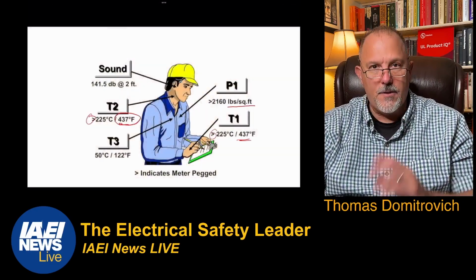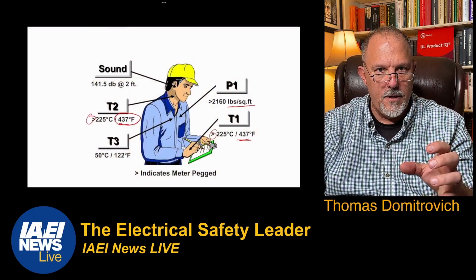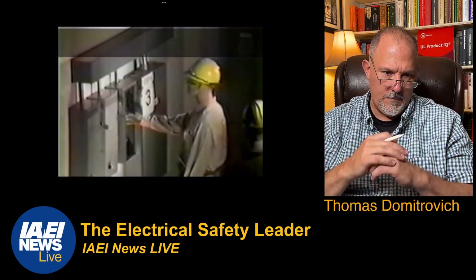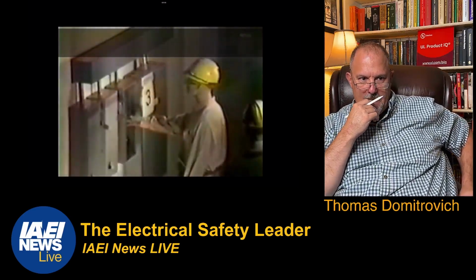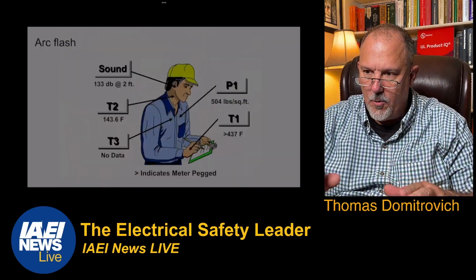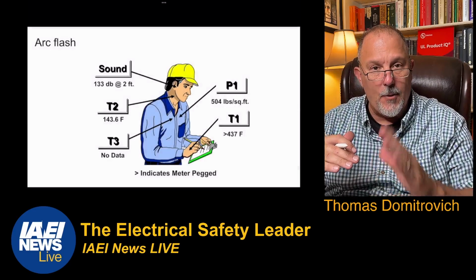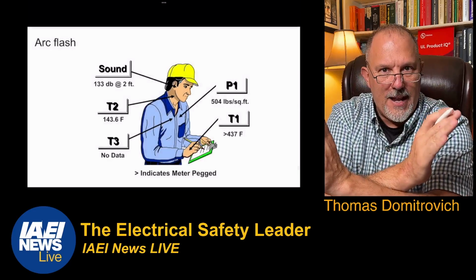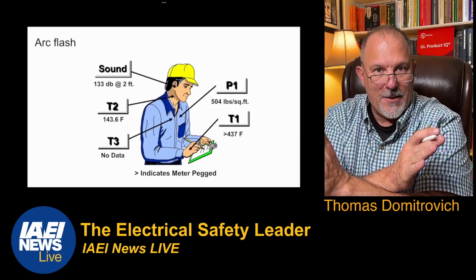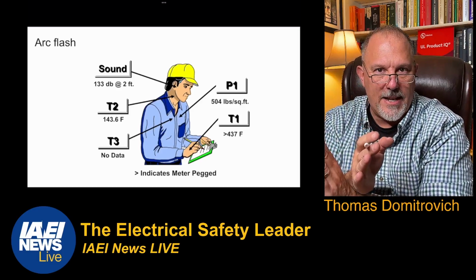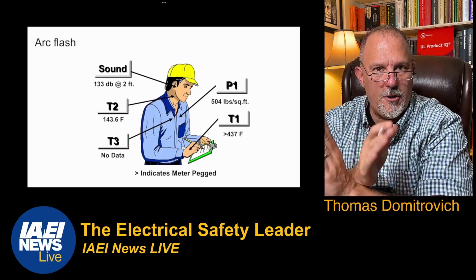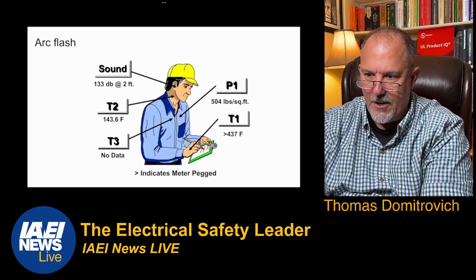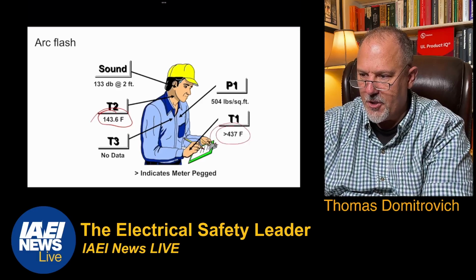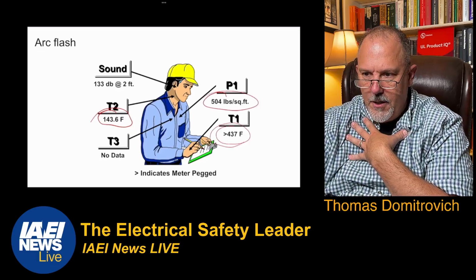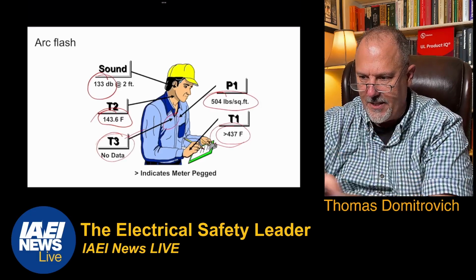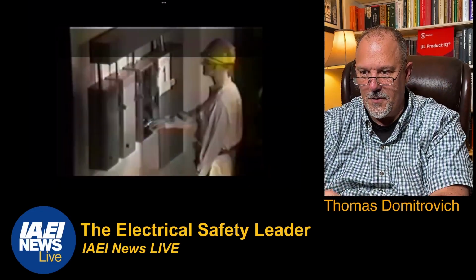Now the next video basically puts a faster clearing time on this device. There it goes. So all I did was reduce the clearing time. I kept the fault currents the same, but I moved the curve to the left. I put a smaller fuse in series. That's like taking a power breaker and putting in a molded case in its place. You've made the overcurrent device act faster. And I got lower temperatures. Temperature of the hands was still up there. Lower pressure, lower dBs, and lower temperature at the chest area. Now the next one is an even faster acting fuse. I've got to zoom in for this one.